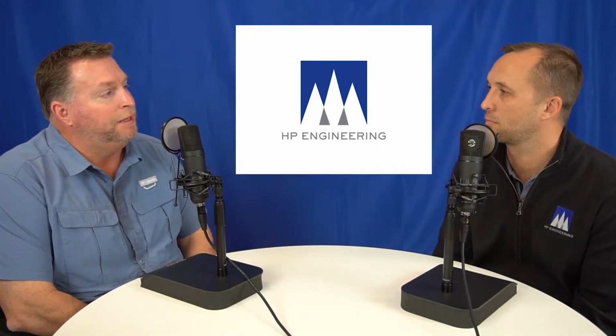You're welcome. If you could start, tell us a little bit about what an energy model is, how it relates to what we do every day, and why it matters. An energy model is an extension of the heating and cooling calculations that are done on every building to determine, for example, the number of tons of cooling that a building needs. But it goes further than that in that it looks at the occupancy schedule, the type of work that's being done in the building, and it actually predicts the electricity, the natural gas, and water utility bills for each month throughout the course of a year.